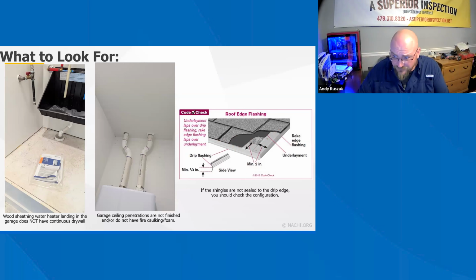Rick did state, so these gaps, a lot of times what the fix is now is that they come in with, instead of drywalling and mudding and all this stuff, they just come in with fire rated foam. Now, I will tell you, there is a lot of controversy going on with fire rated foam right now. There is a lot of fire rated foam on the market, but there is only very specific fire rated foam that actually meets fire rating standards for this application.